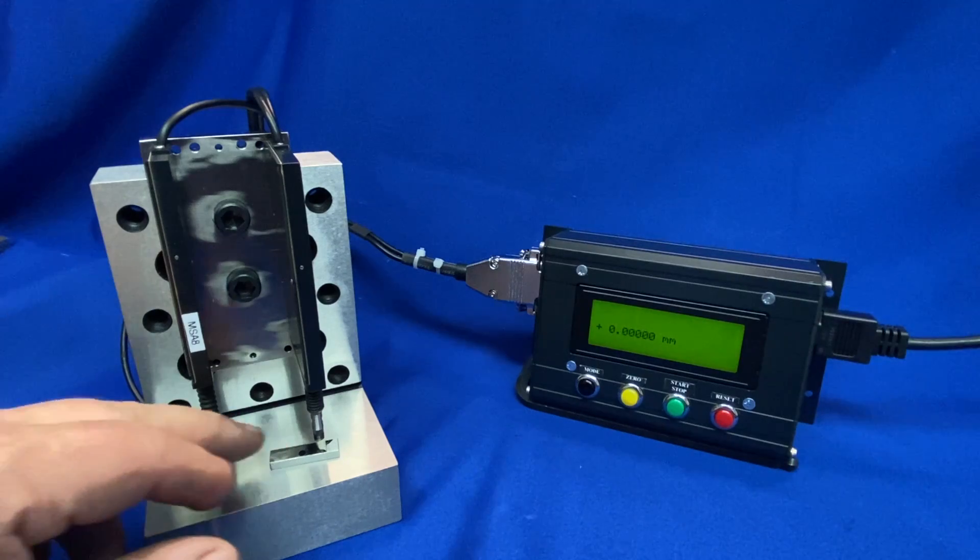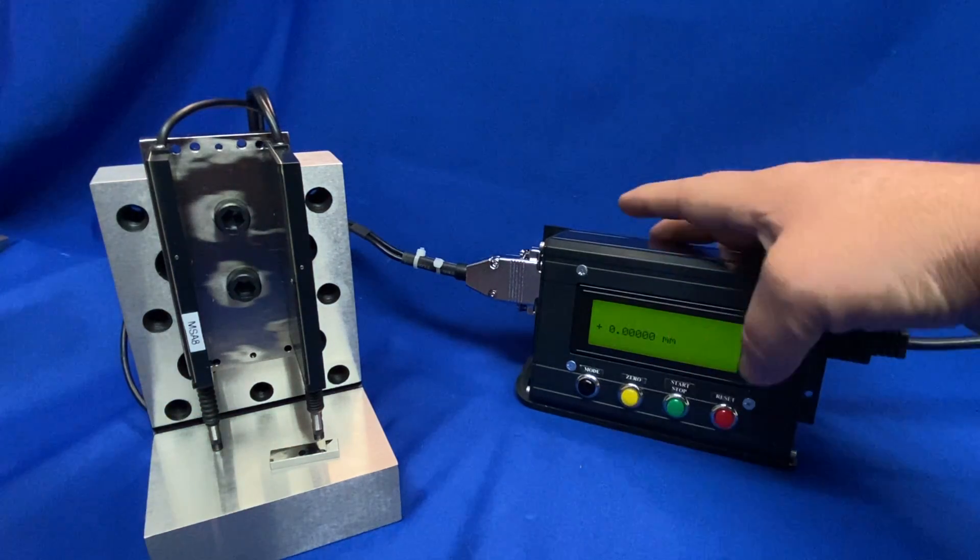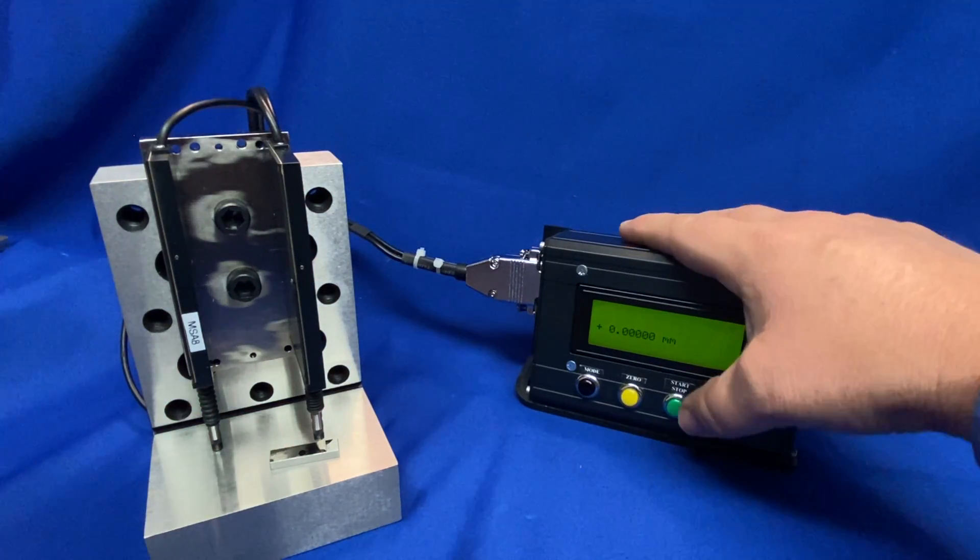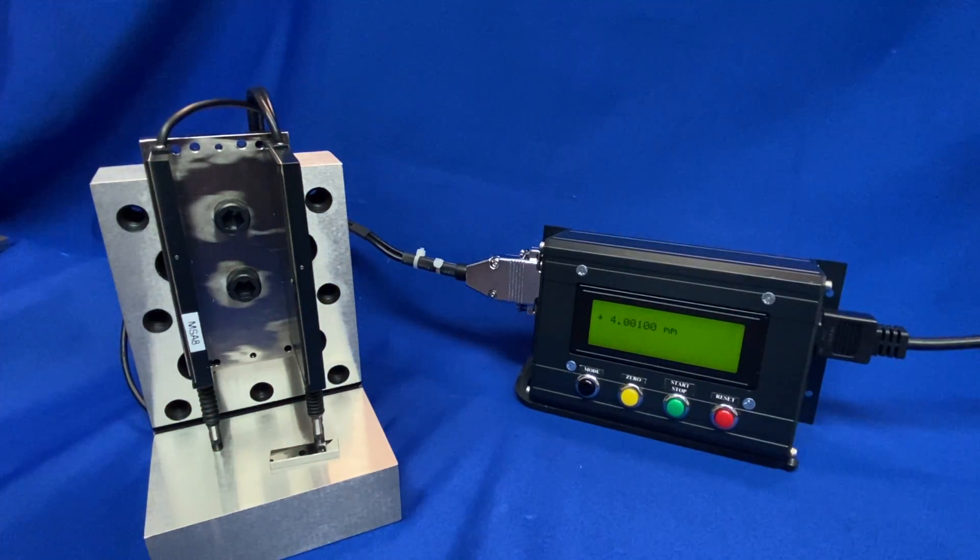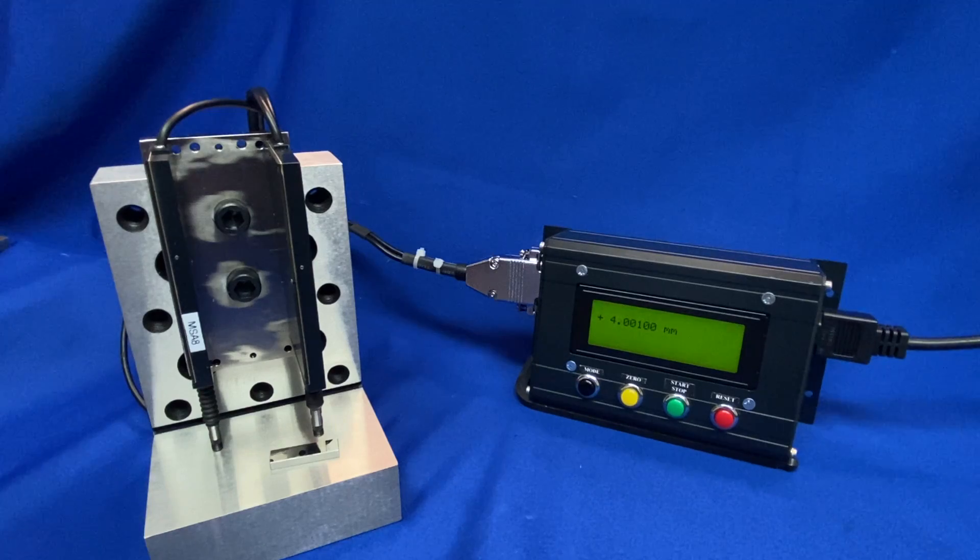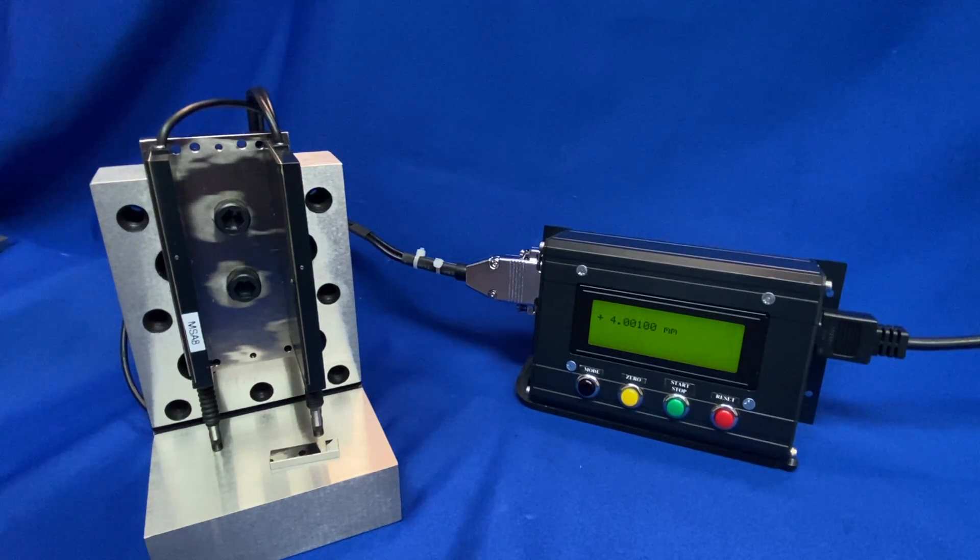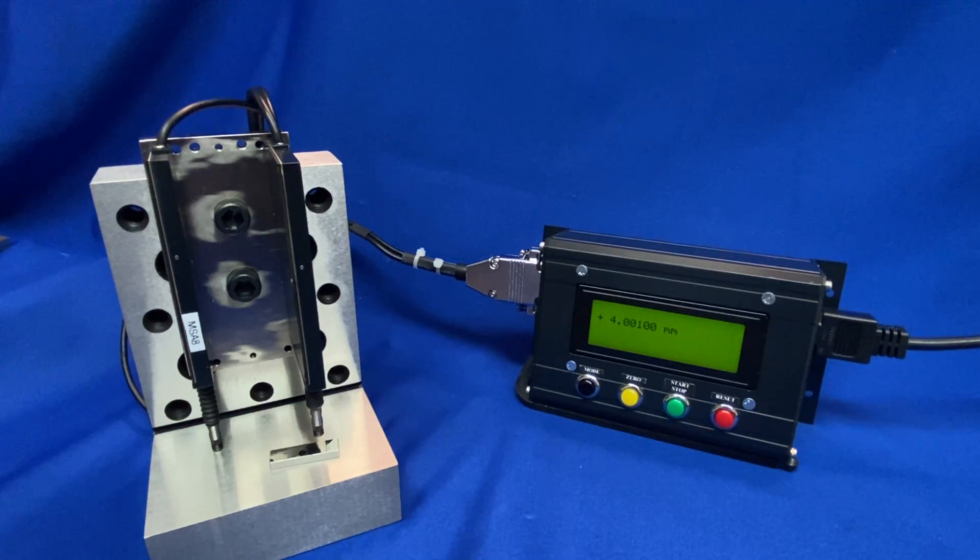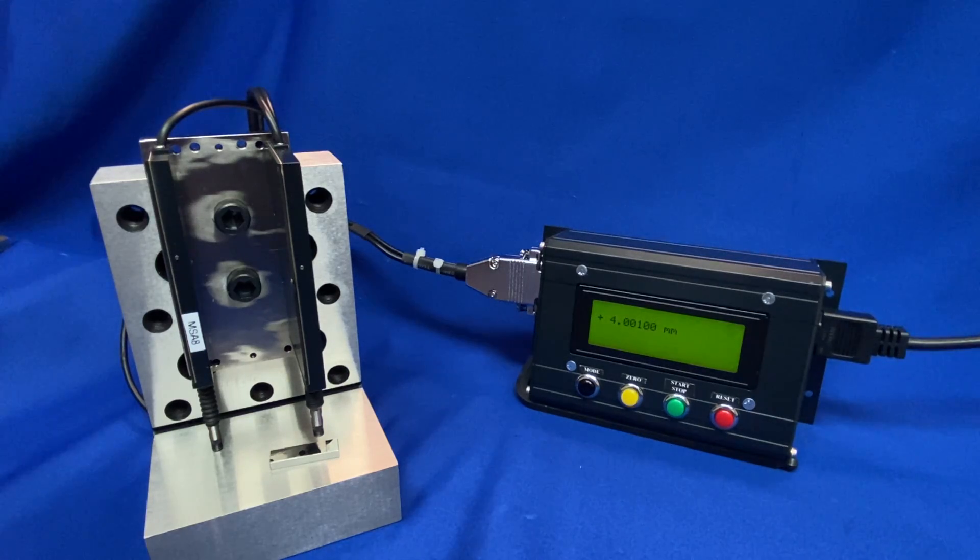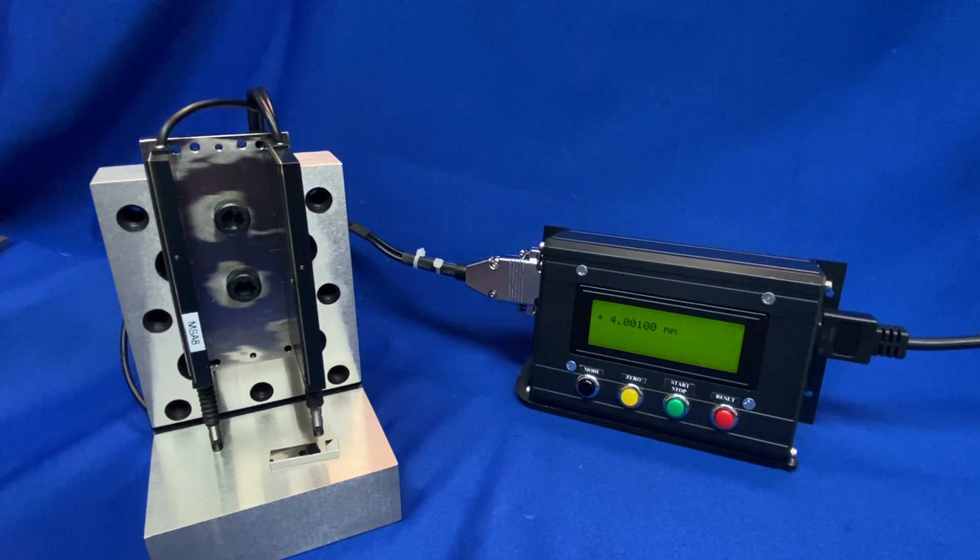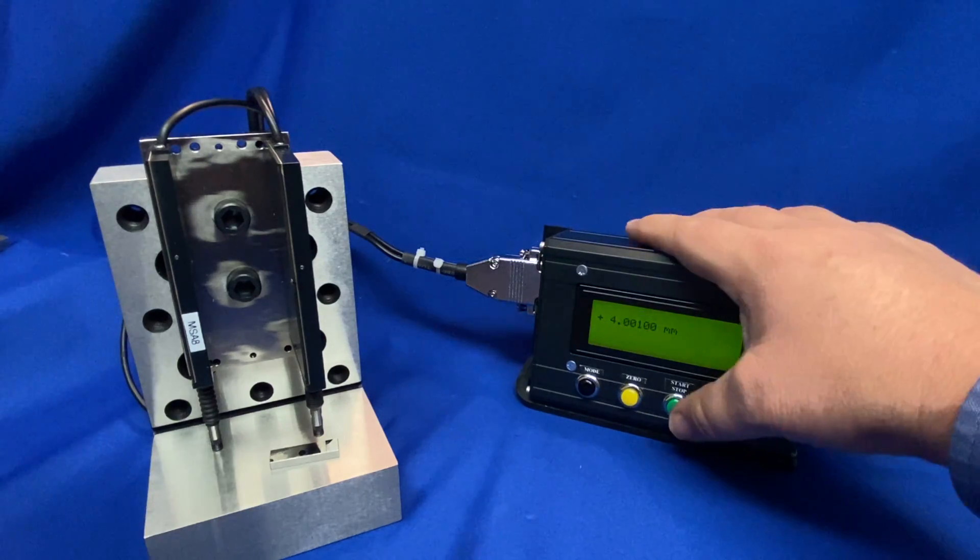We'll slide the gauge block in place. We will measure that. Start button and there we have our measurement. This is a 4 millimeter gauge block as it's displaying 4.001. So 4 millimeters and 1 micron is what it's reporting to us.